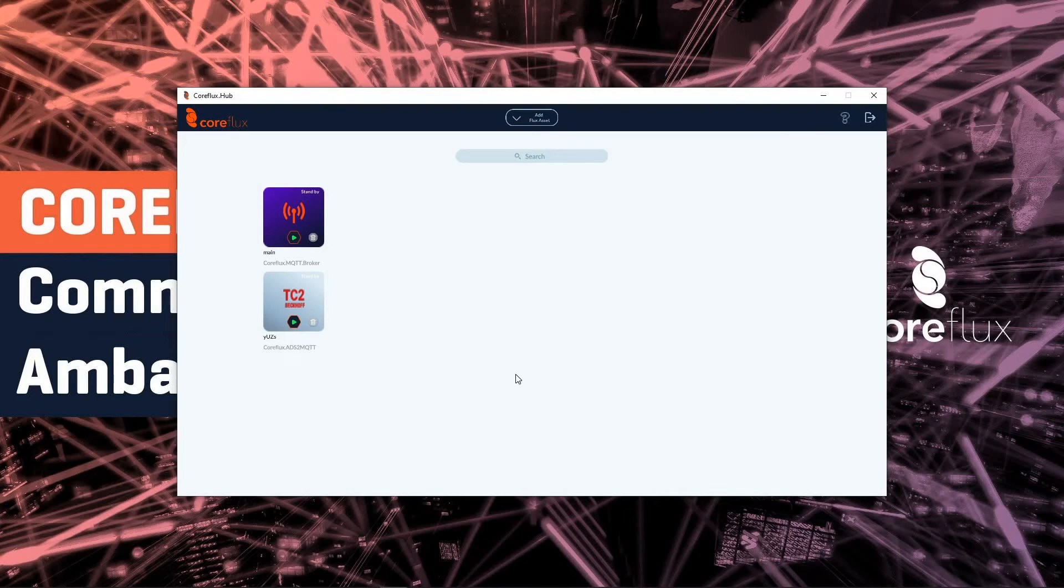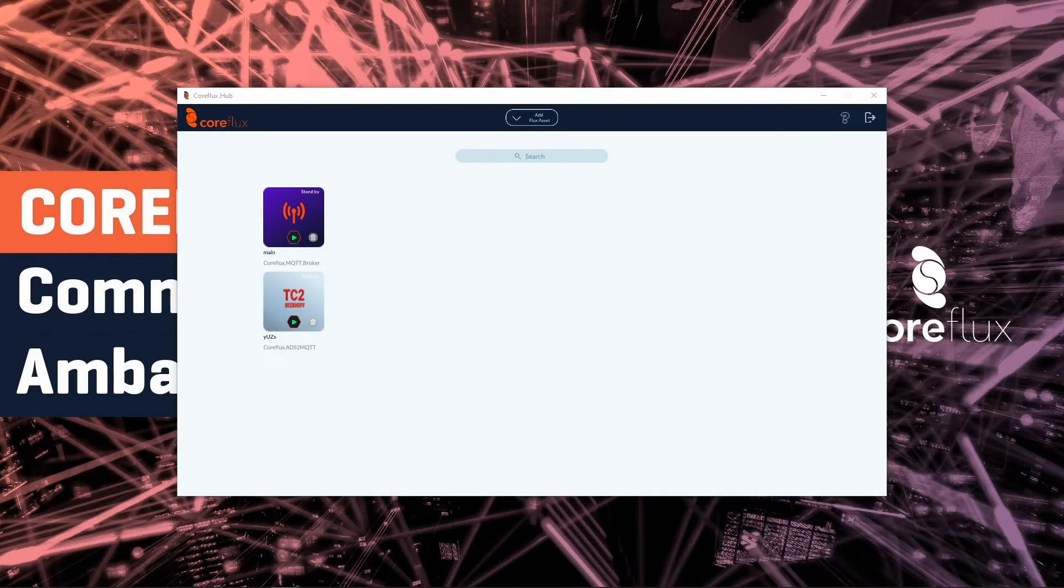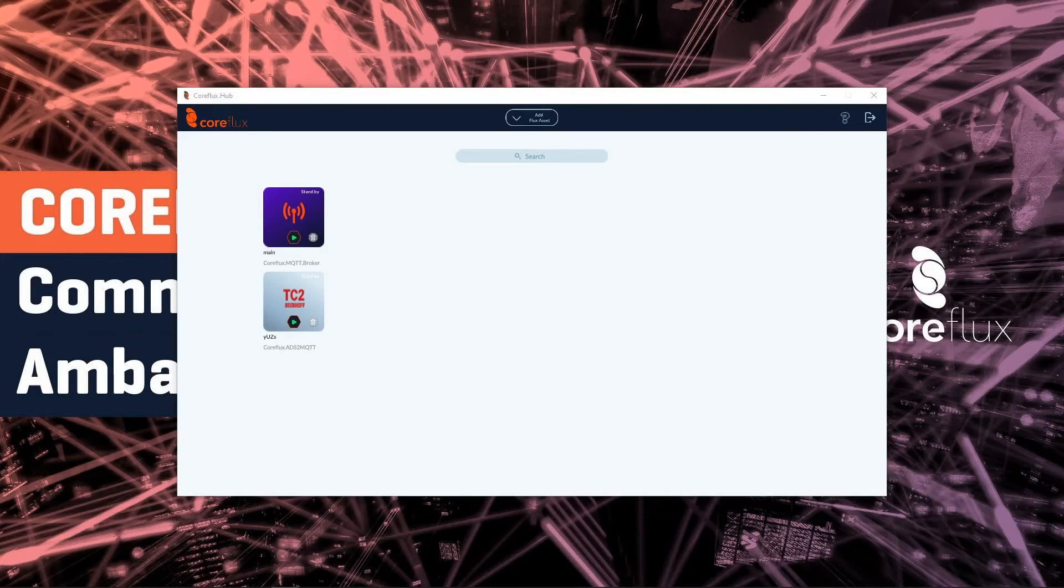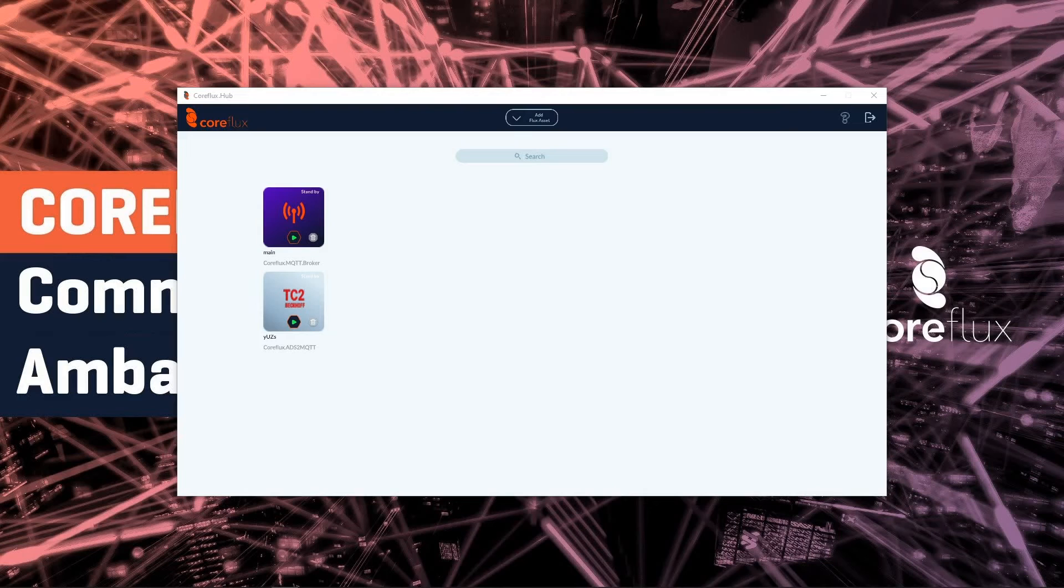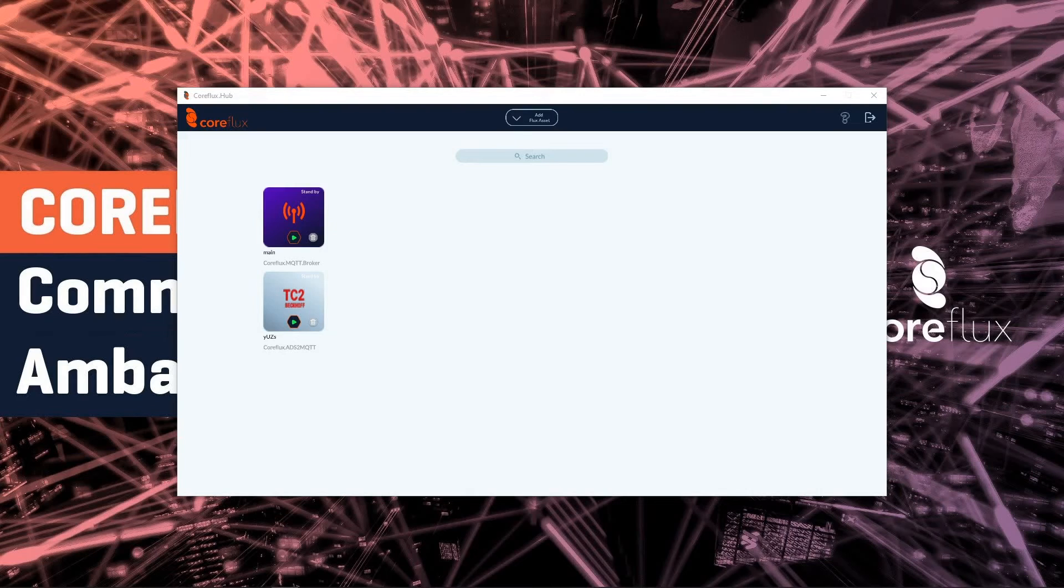We have two CoreFlux assets here. One is a functional asset which is the MQTT broker that provides us with a broker so other clients can publish and subscribe MQTT variables. On the other side we have a CoreFlux asset that brings variables into the MQTT broker from a TwinCat device. In this case it's a TwinCat2 device where we are able to get the data.